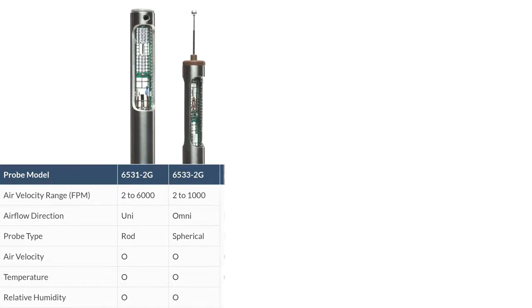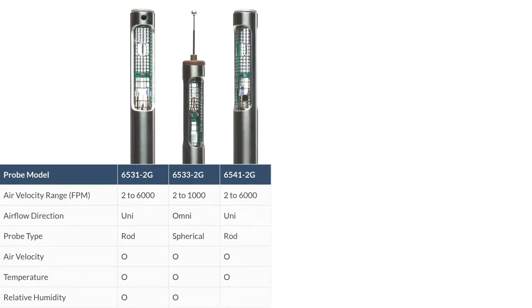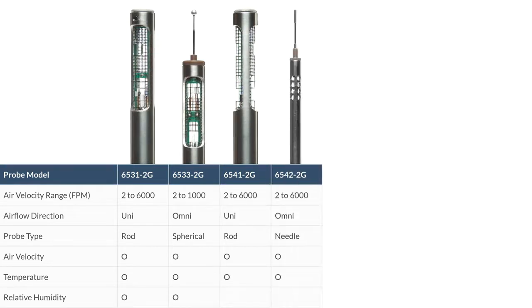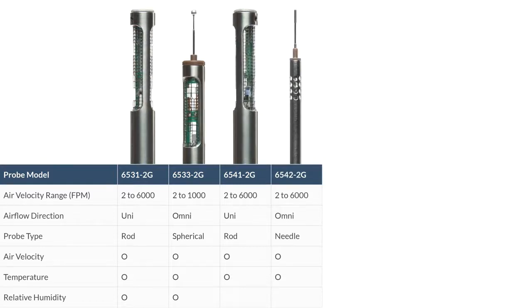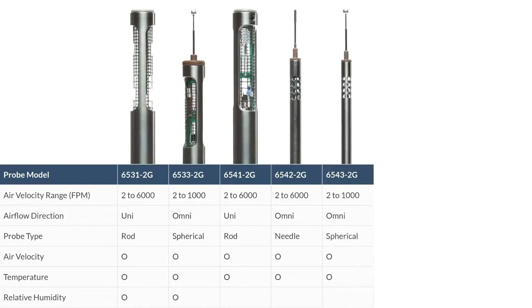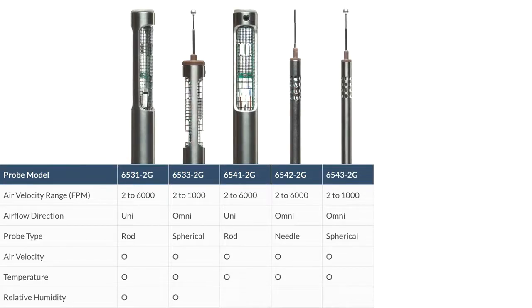Probe model 65412G is a unidirectional rod-type probe capable of reading air velocity and temperature within an air velocity range of 2 to 6,000 feet per minute. Probe model 65422G is an omnidirectional needle-type probe capable of reading air velocity and temperature within an air velocity range of 2 to 6,000 feet per minute. Probe model 65432G is an omnidirectional spherical-type probe capable of reading air velocity and temperature within an air velocity range of 2 to 1,000 feet per minute.